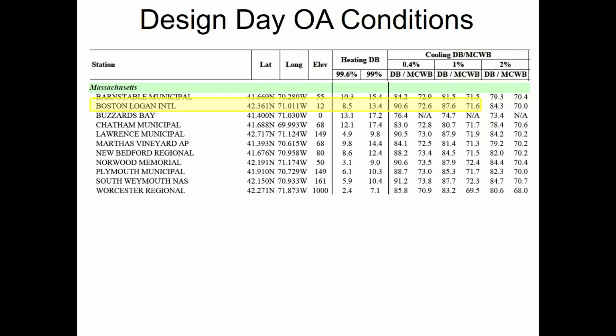So if I look at ASHRAE, which is what almost everybody uses, I'm looking at Boston for our example here in yellow. There are two heating numbers, 99.6 and 99. The code doesn't say which one you have to use, right? It just says you have to use ASHRAE, so I can use either one. What 99 means is 99% of the year it's going to be warmer than that number, meaning 1% of the time it's less. 99.6 means 0.4% of the time it's below that number. So 0.4% of an average year, on a 30-year rolling average, it's below 8 degrees in Boston.